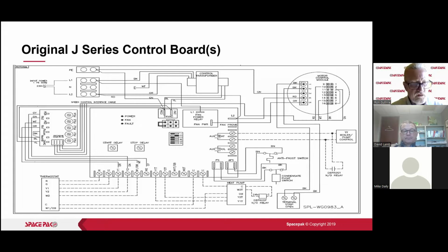Basically, what we were doing is we were setting the volts DC, and we were measuring in volts DC. We were setting the volt DC signal that would be sent to the motor head, 0 to 5 volts, and that would control the speed of the motor. So we had to do that manually. We had to look at a chart that will come up and determine where we needed to be as far as the signal that we are sending to the motor head.